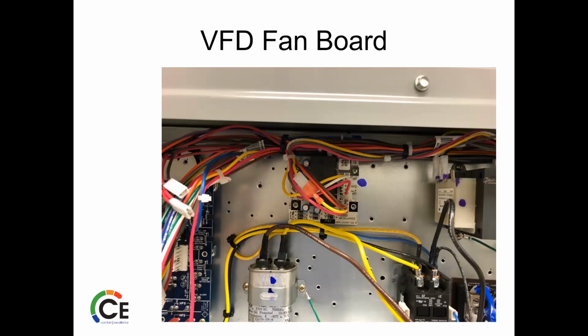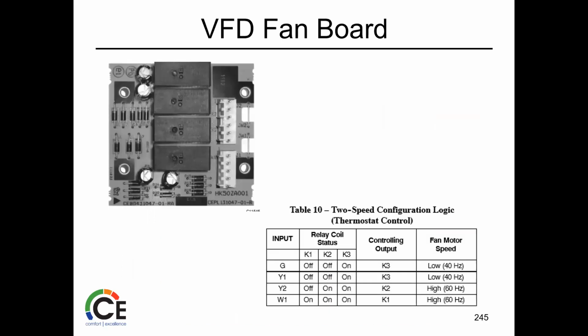The VFD fan board. Again, this is just a small control board from the main control, which sends the signal to the VFD to start to operate. So again, we got a Y1 call, and I'll show this in the schematic in a minute, but the K1 and K2 relays are off. K3 is on. You're going to get low speed fan. Once we get a Y2 call, then the K2 and K3 relays are on, and then you're going to get high speed. If you have heating, you're going to get high speed right away. And if you're just doing fan, you're going to get low speed.